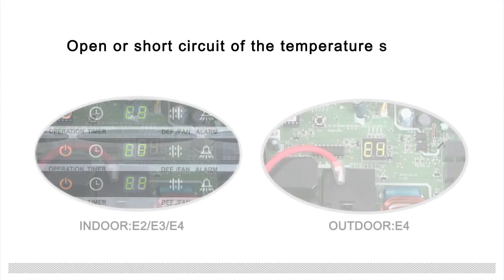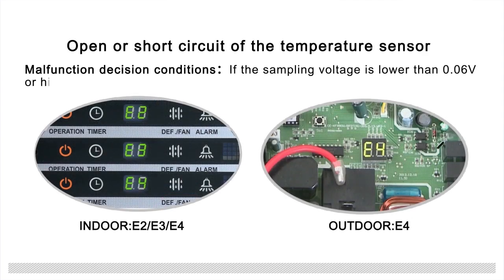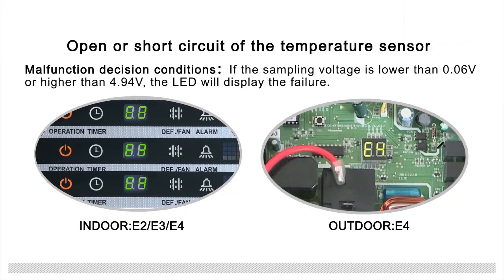Open or short circuit of the temperature sensor. Malfunction conditions: if the sampling voltage is lower than 0.06 volts or higher than 4.94 volts, the LED will display the failure.